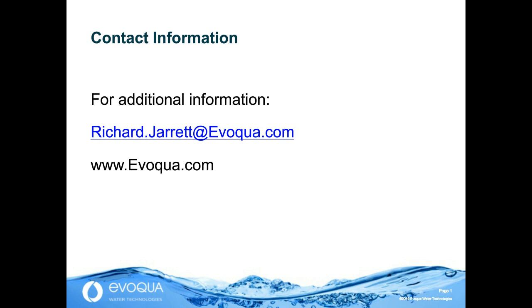Okay, thank you. So next question, what is the molecular weight cutoff for UF membranes? Well, there's a very wide range in UF, and some manufacturers put molecular weight cutoffs as low as 1,000 molecular weight. Some are rated at 6,000, 10,000, 80,000, 100,000. And I have seen from operational systems ultrafilters rated as high as 80,000 molecular weight cutoff, providing a 4-log reduction or better of endotoxin. So in my personal experience, I don't find that the molecular weight cutoff is important.